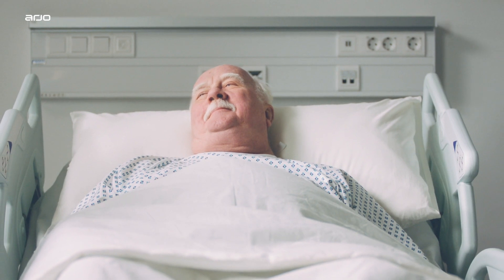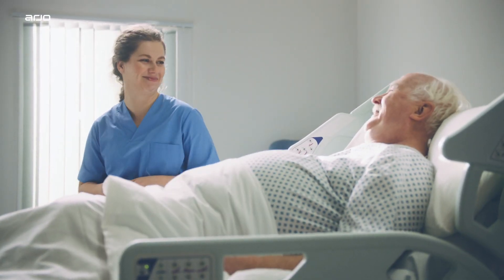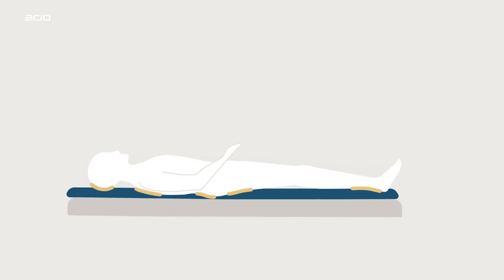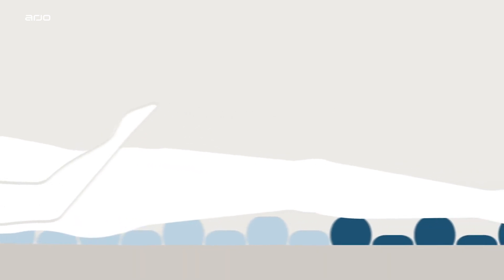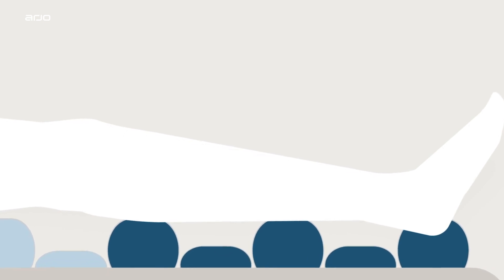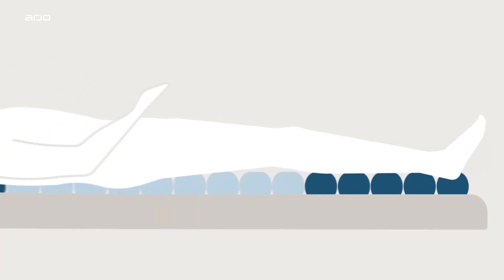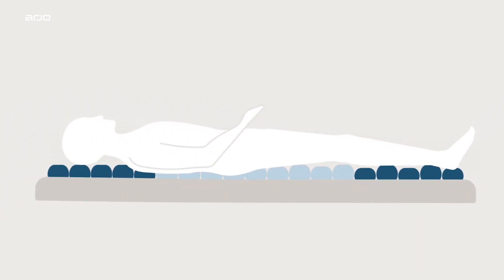Tailoring therapy with intelligent, continuous and automated pressure adjustment: Self-set technology. Self-set technology, or SST, incorporated into the Auralis system is capable of automatically sensing and adjusting the mattress cell pressures, and is designed to prevent incorrect pressure selection during active and reactive therapy modes, irrespective of patient weight or position.